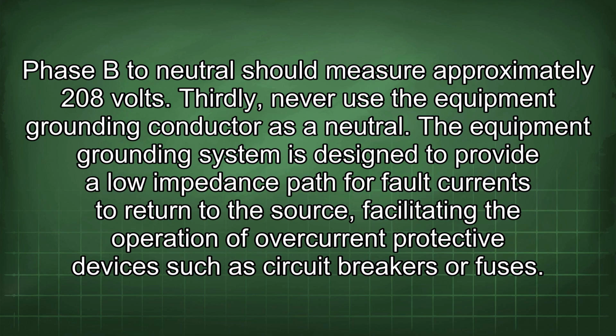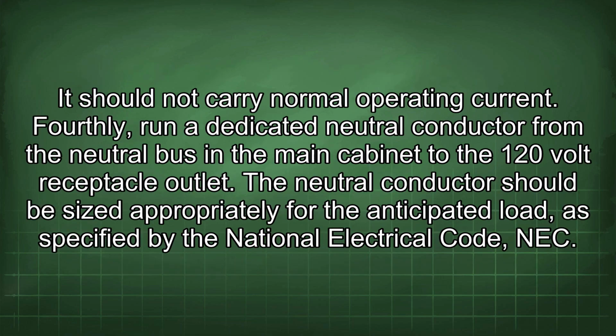Thirdly, never use the equipment grounding conductor as a neutral. The equipment grounding system is designed to provide a low impedance path for fault currents to return to the source, facilitating the operation of overcurrent protective devices such as circuit breakers or fuses. It should not carry normal operating current.